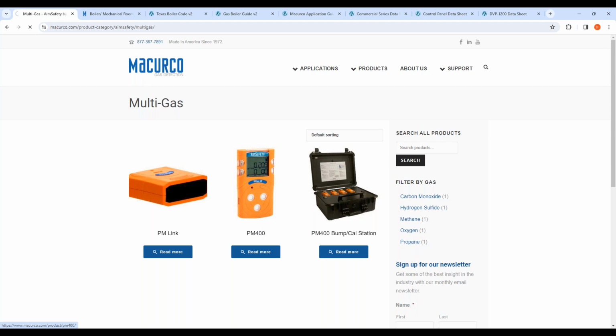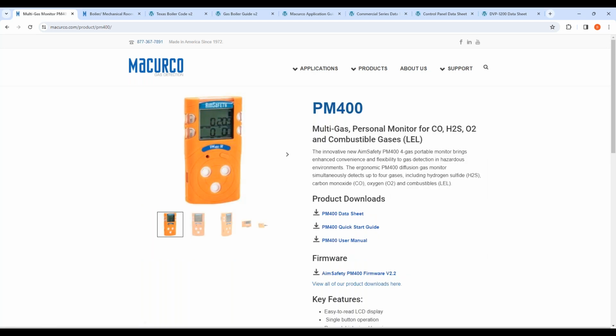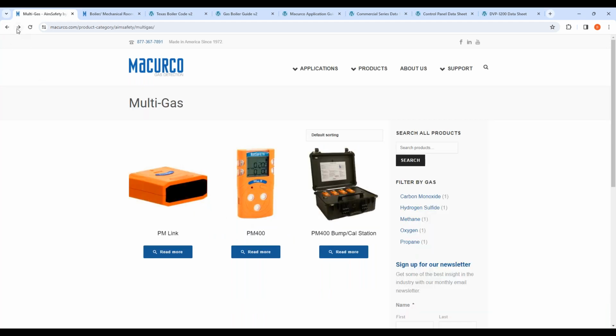The reason why this is important is there's 2 models here: an IR model, and I'll show you here real quick. So it'd be called the PM400 IR or the PM400P, that's the only 2 options available, and it's all found within our data sheet here. Most commonly seen is the P, it's called the cat bead sensor. It's a little bit more cost affordable, so it makes sense in terms of meeting the code. Going back a little bit, the bump cal station, these guys right here, you can calibrate and bump test these units within this station.